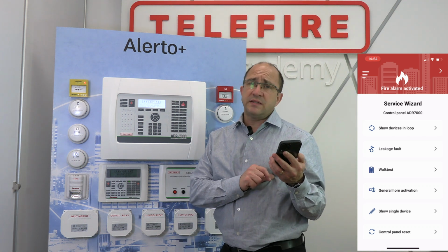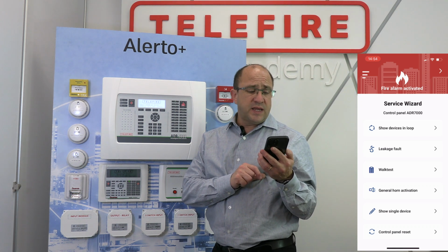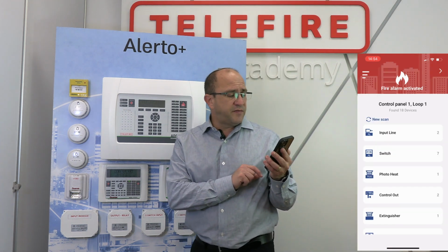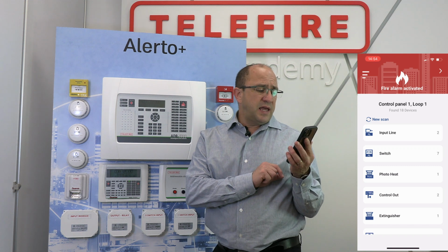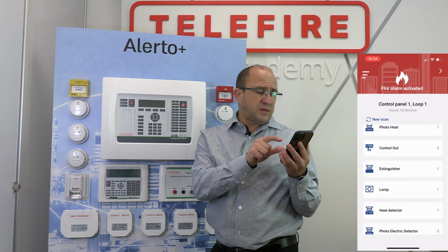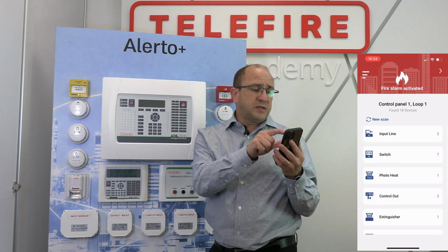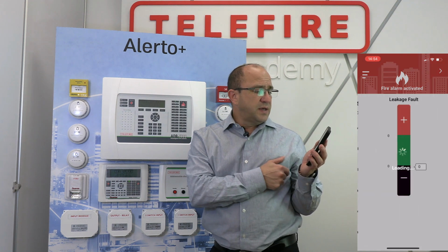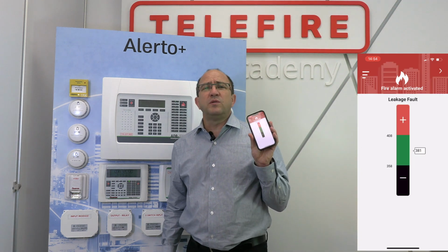I can show devices in loop. I can see a leakage fault. Let's see devices in loop. Loop number 1. I have 2 input lines. I have 7 switches, 1 photo heat detector, control out, whatever. Let's go back one stage. Leakage fault. This shows me the ground fault.